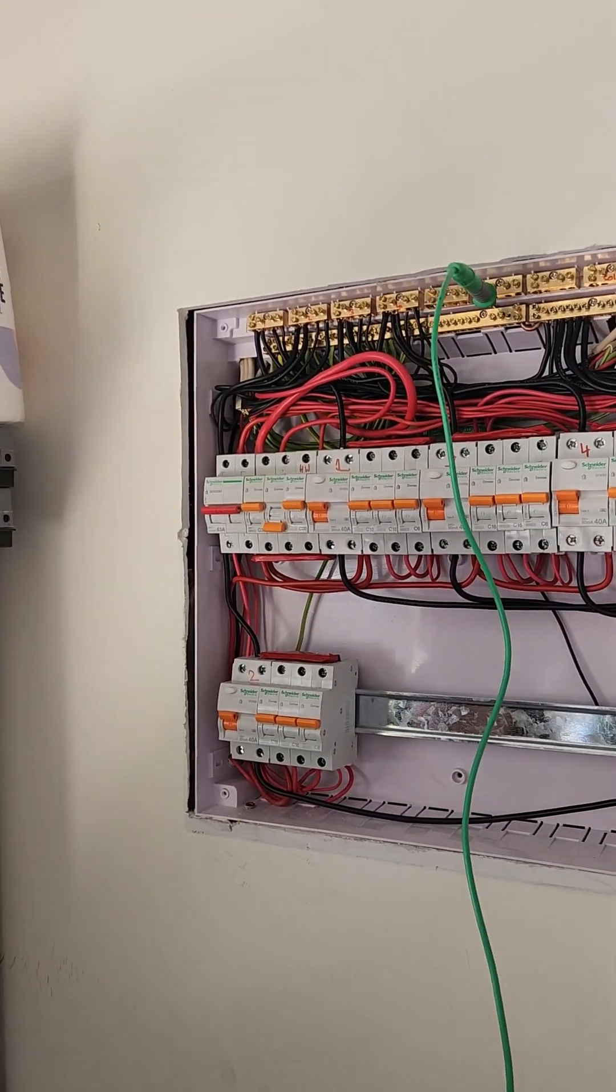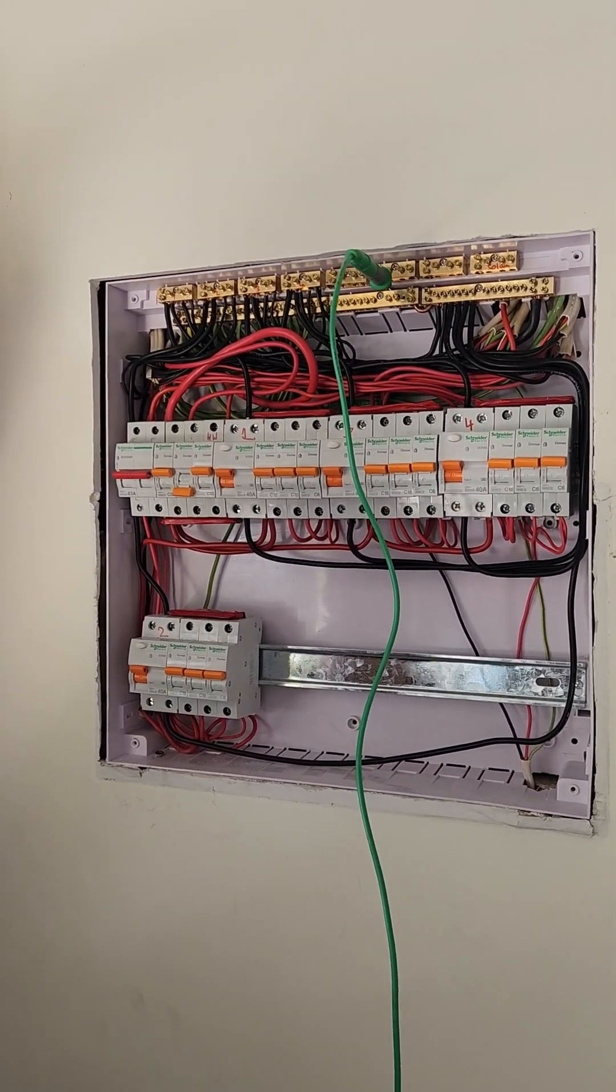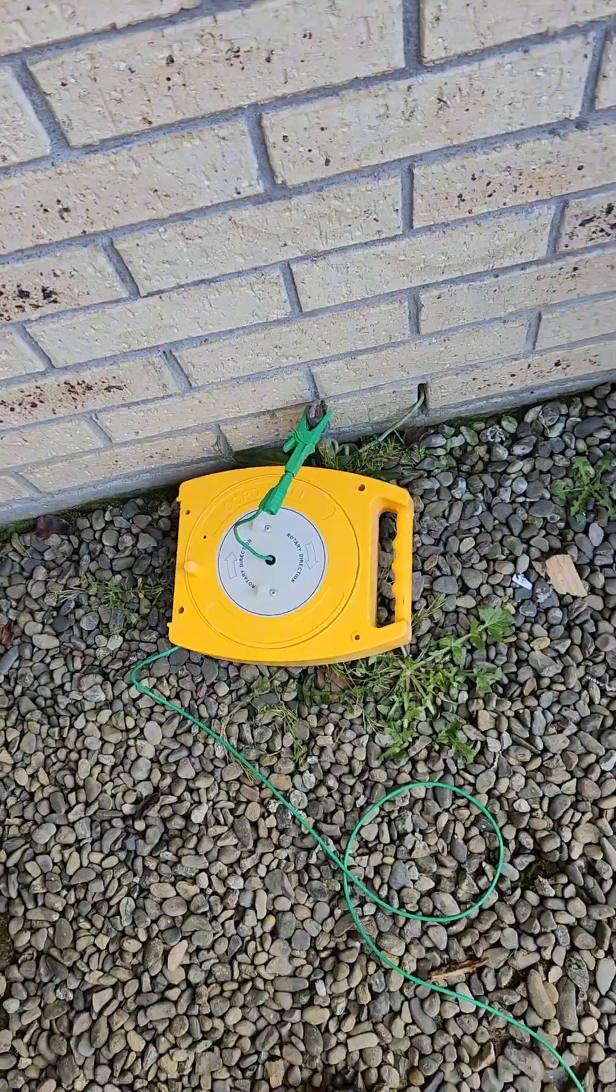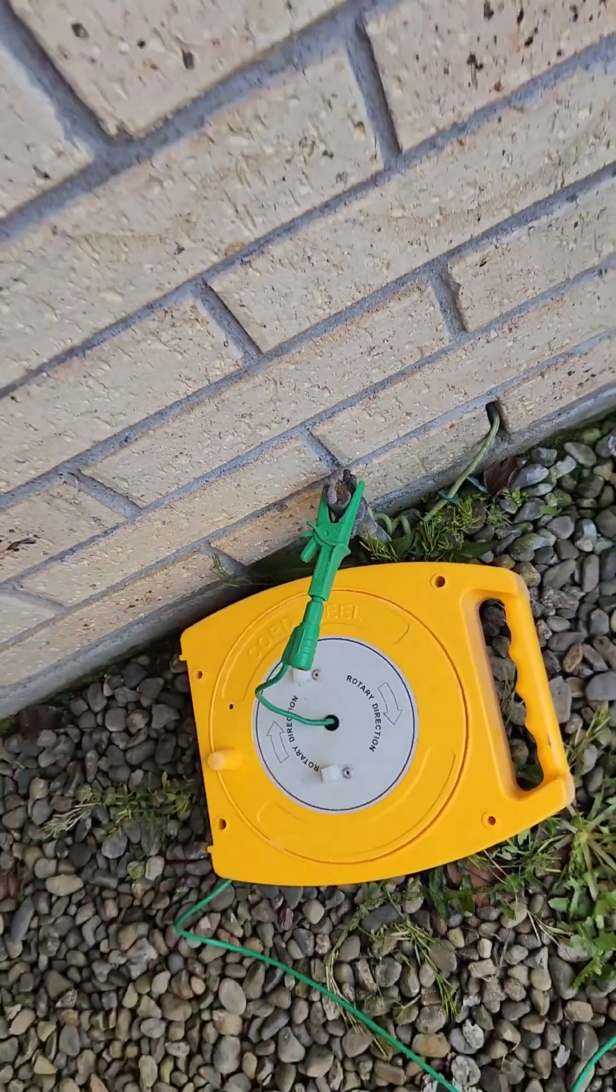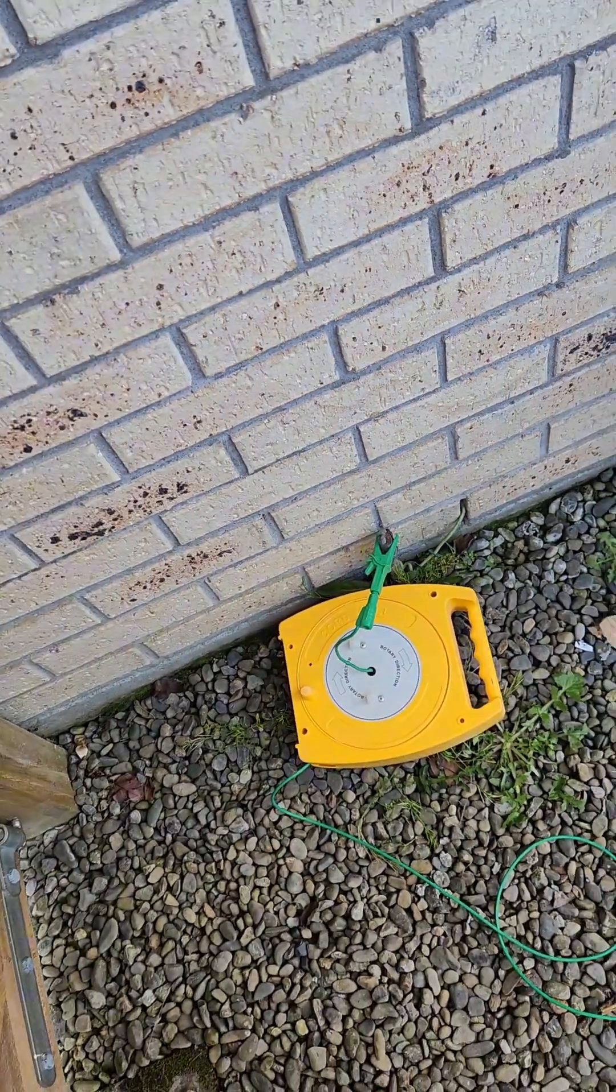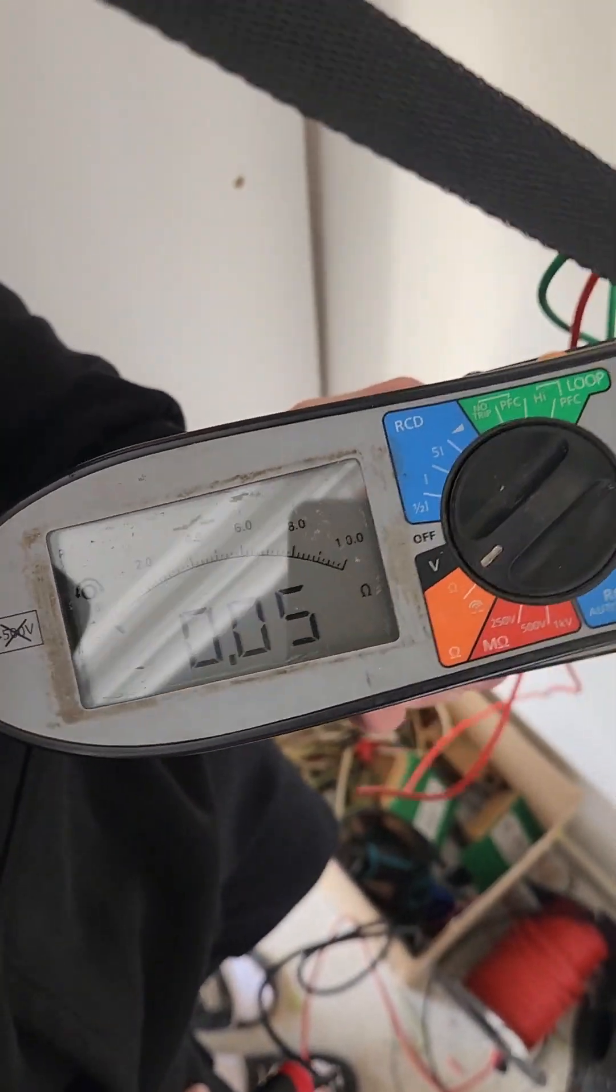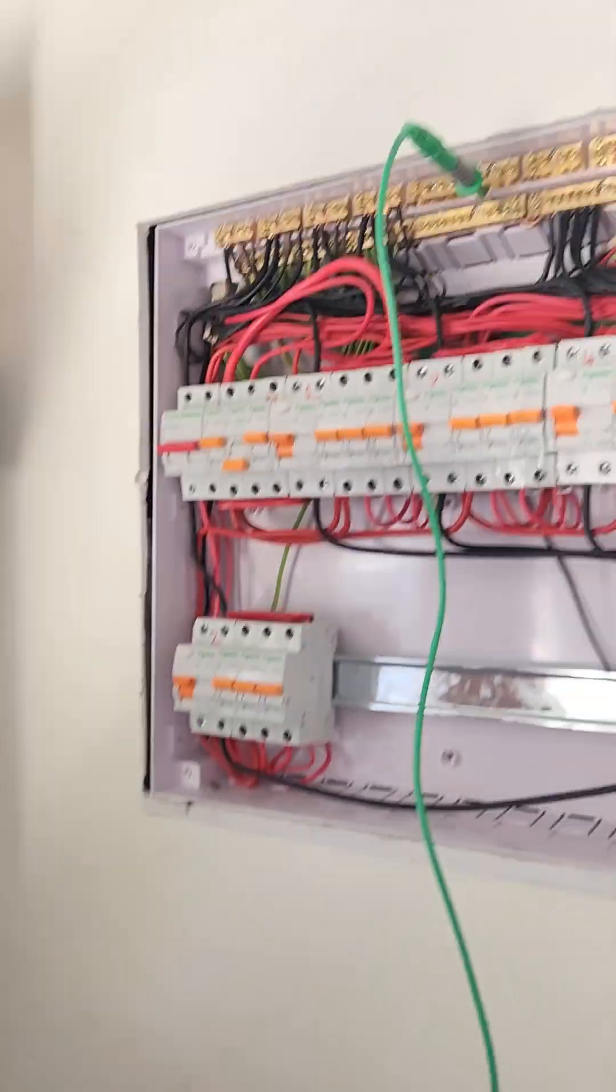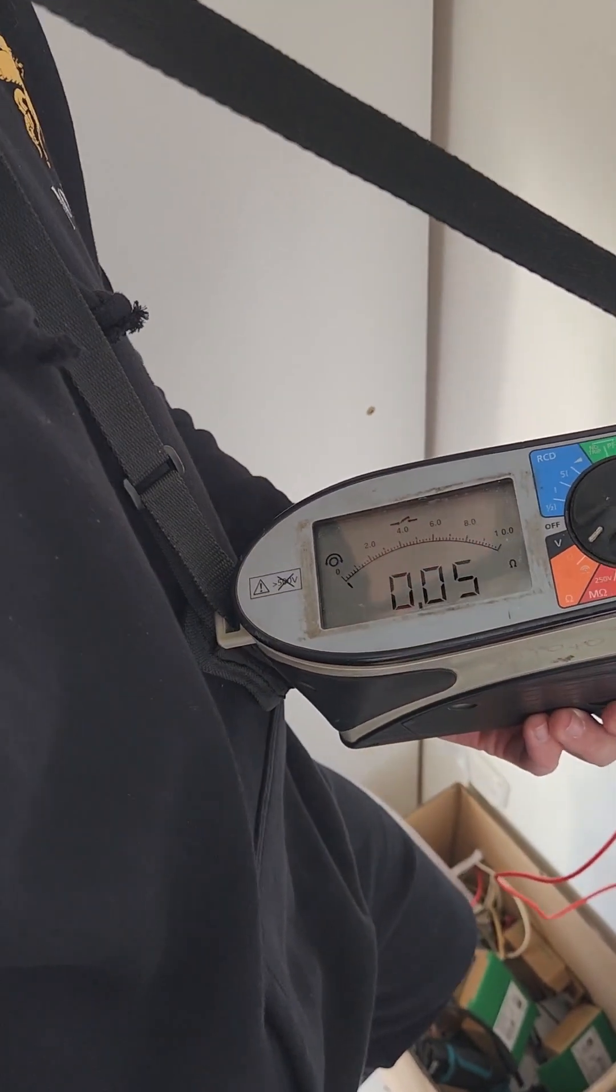Next thing we will do is we'll run a fly lead out and we'll test the main earth. It's not required because we've just done a switchboard upgrade, but we'll check it anyway since we are in the midst of testing things. I've got my fly lead attached there, goes off into the house. Okay, we've just turned it on to ohms, and we are at 0.05 of an ohm, and the maximum for a main earth is 0.5 of an ohm, so we are well and truly below regulation.